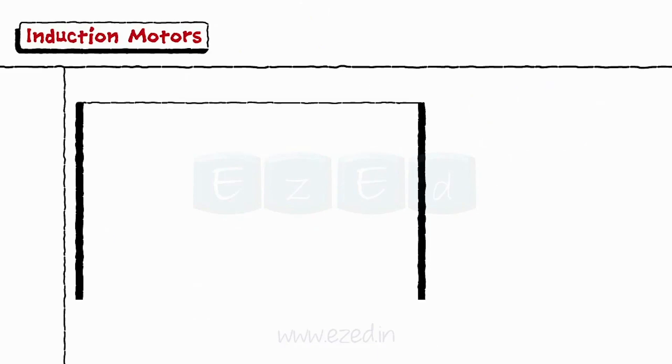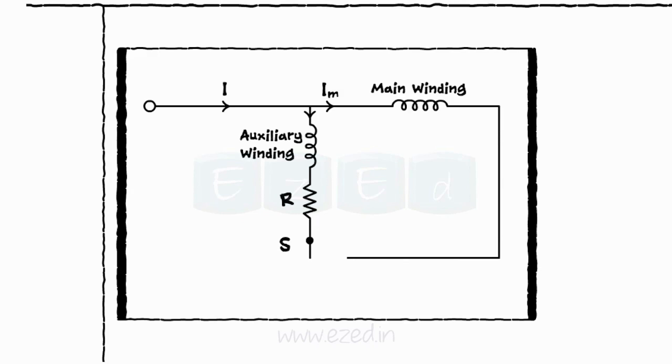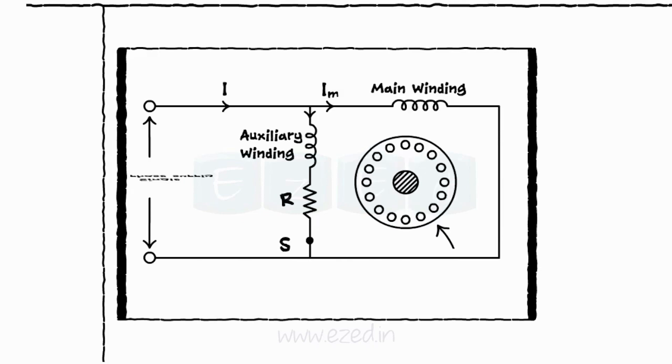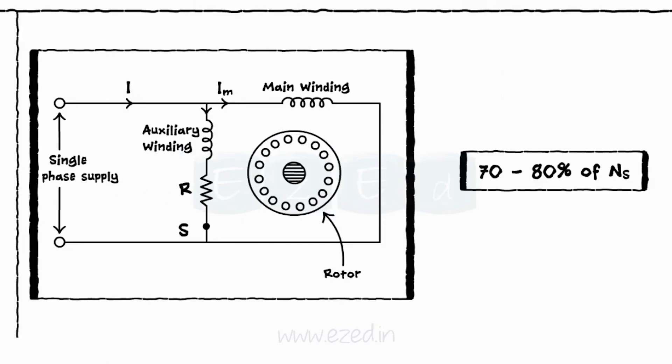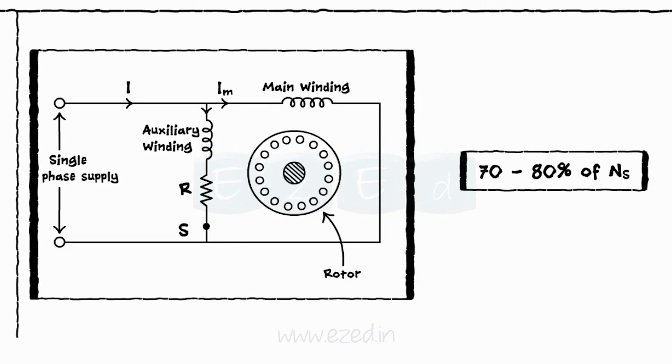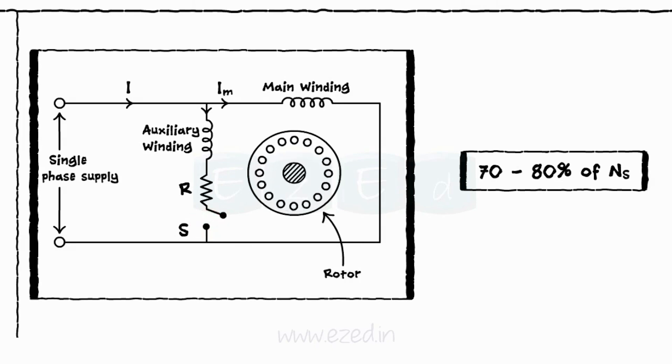A centrifugal switch is connected in series with the auxiliary winding and is located inside the motor. Once the motor reaches the speed of 70-80% of synchronous speed, the starting auxiliary winding is disconnected from the supply with the help of the switch.